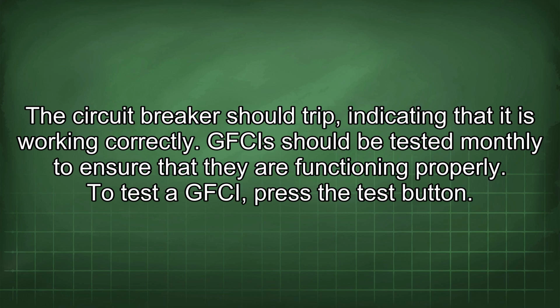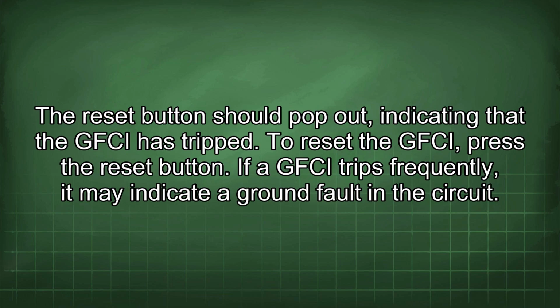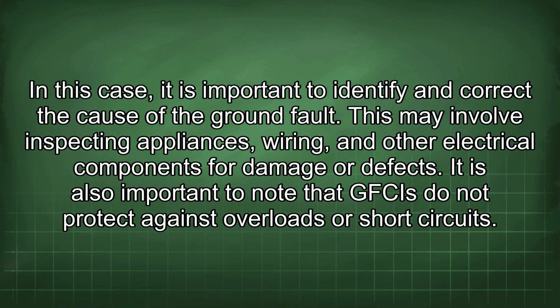GFCIs should be tested monthly to ensure that they are functioning properly. To test a GFCI, press the test button. The reset button should pop out, indicating that the GFCI has tripped. To reset the GFCI, press the reset button. If a GFCI trips frequently, it may indicate a ground fault in the circuit. In this case, it is important to identify and correct the cause of the ground fault. This may involve inspecting appliances, wiring, and other electrical components for damage or defects.